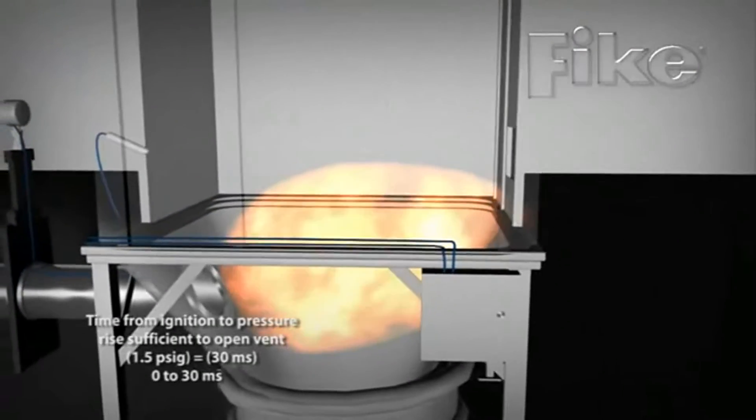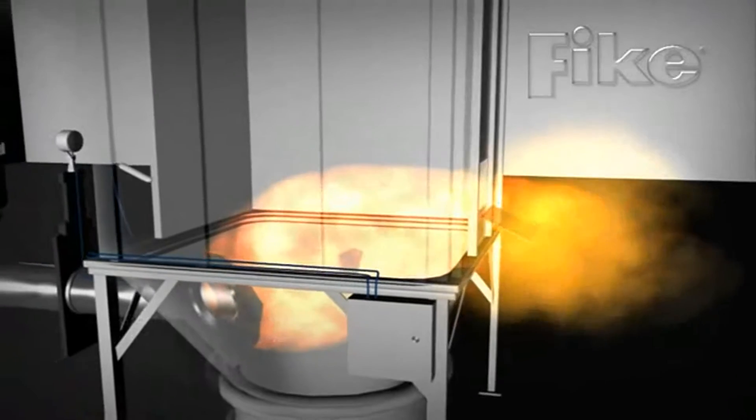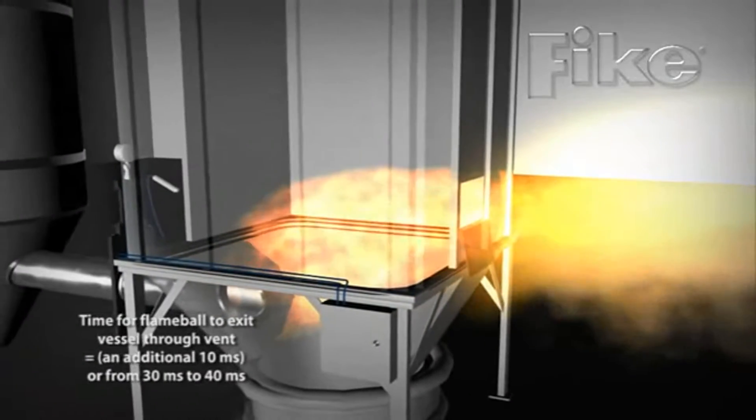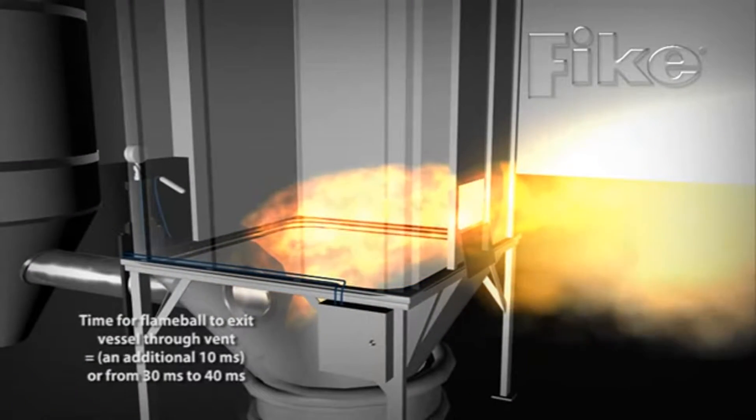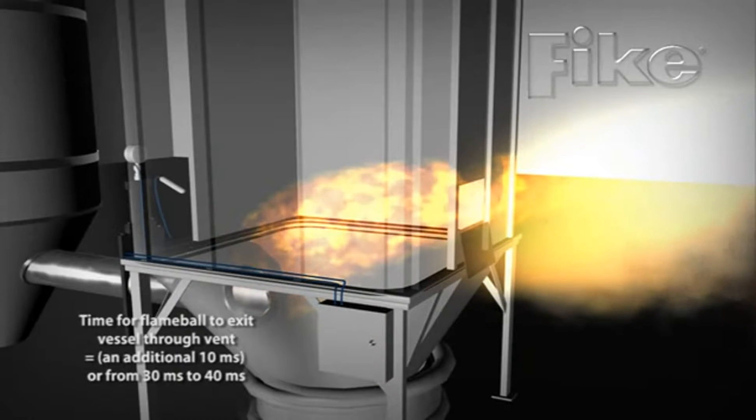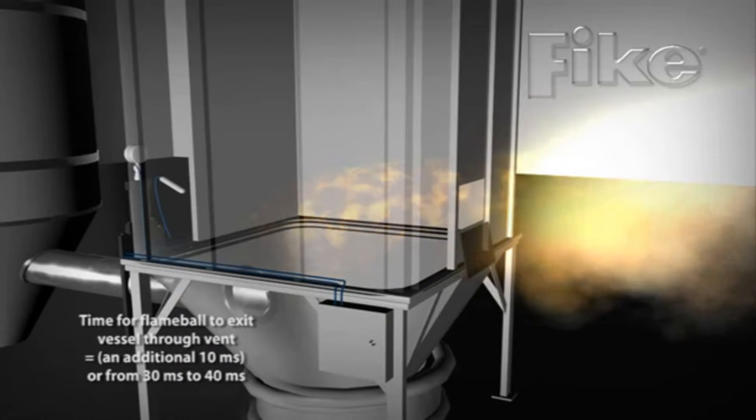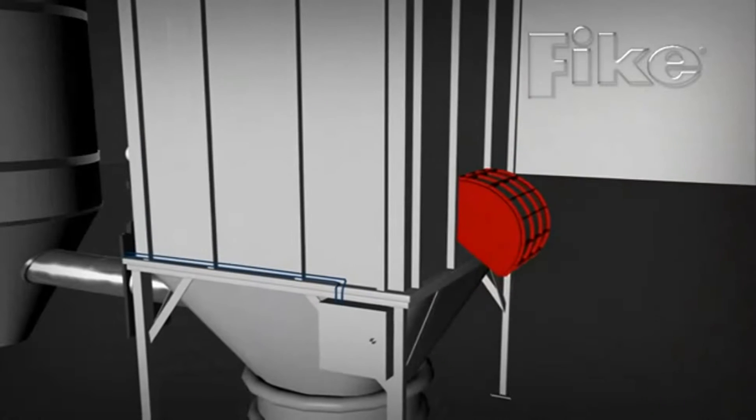The explosion vent ruptures at a preset pressure, limiting the stress on the vessel and allowing it to maintain structural integrity, while also releasing that pressure and allowing the fireball to vent into a safe area outside the facility.